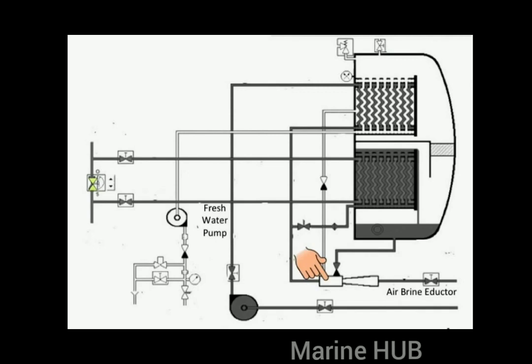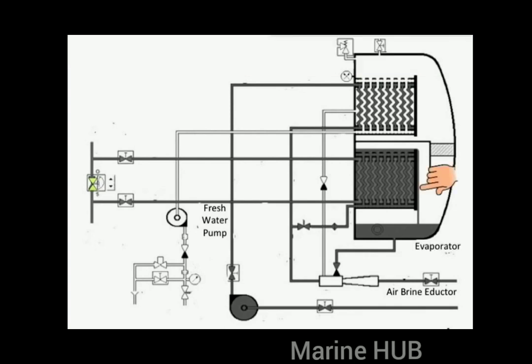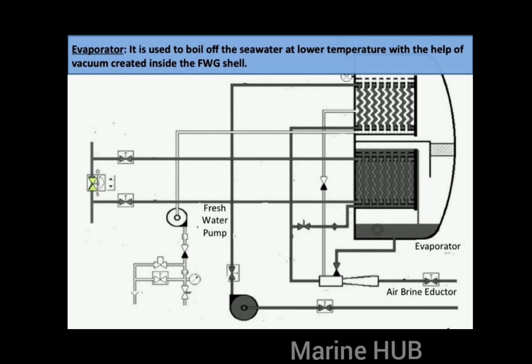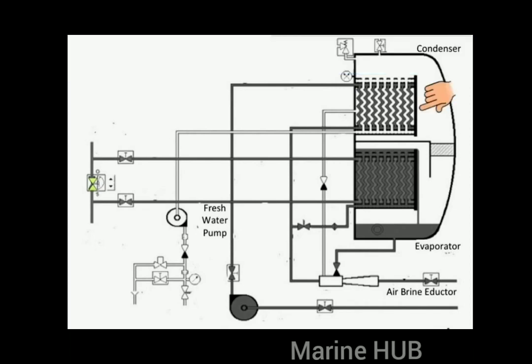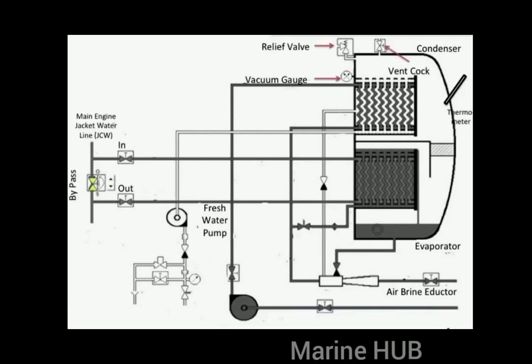The Air Brine Eductor is used to remove the accumulated brine from the generator and to create the necessary vacuum. The evaporator is used to boil off the seawater at a lower temperature with the help of the vacuum created inside the fresh water generator shell. The condenser condenses the fresh water vapors and collects them in liquid form for further use.